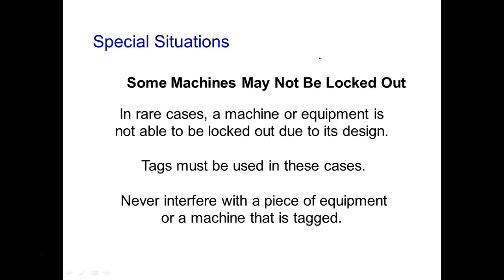Even my disconnect for my air conditioner is inside, so normally, if the disconnect is inside, I forget what the rule is. Within sight, there are some situations where you don't have to lock and tag because the disconnect and the device you're working on are right there together. You understand, you've got a visual on the lock. Still, even if you get into a situation where you can't lock out, you still need to tag out.